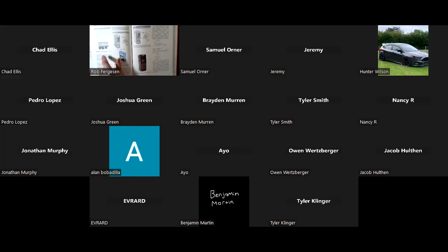Some of the older drives, they're adjustable like this, just like you have on a typical magnetic motor starter. But most of the newer drives have them set up as parameters, in my experience. So you have to set them up ahead of time and program them. And it talks about how you would set them up, usually based on the nameplate of the motor.